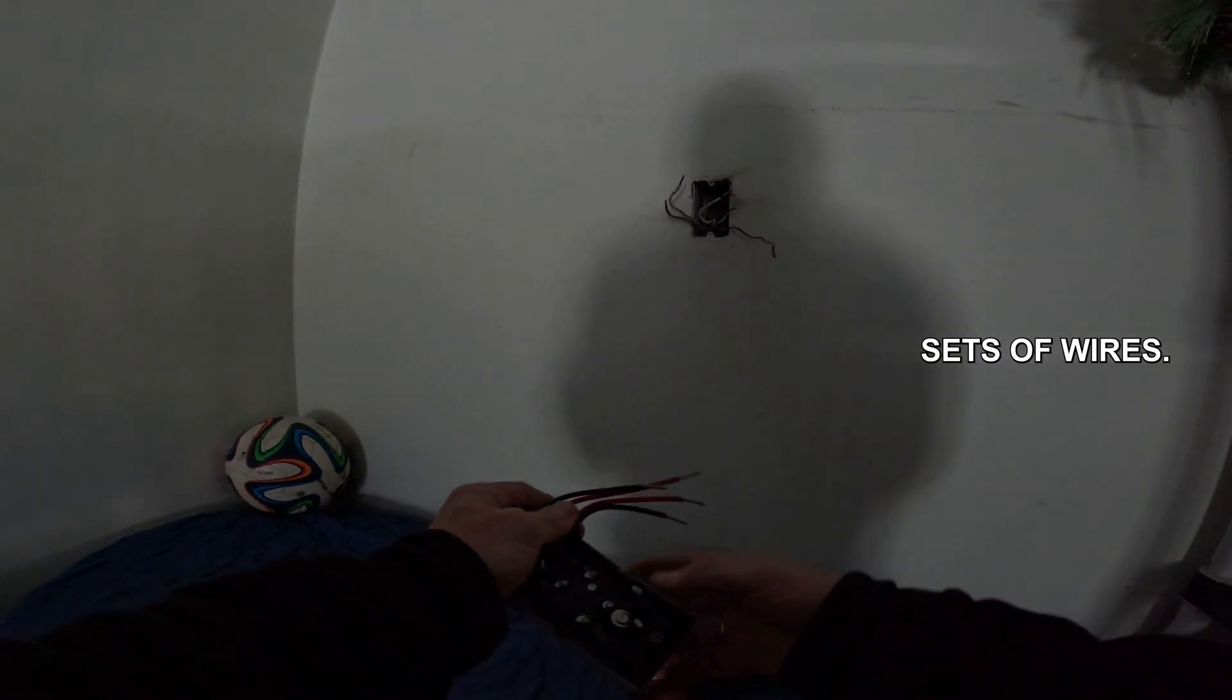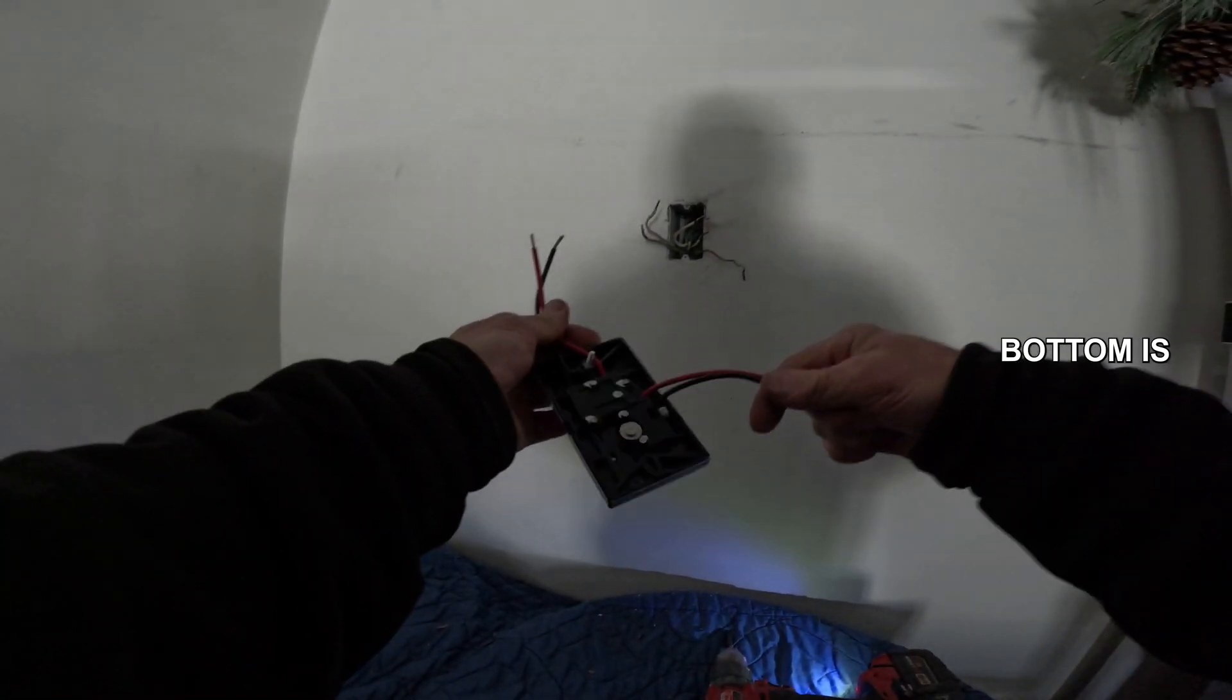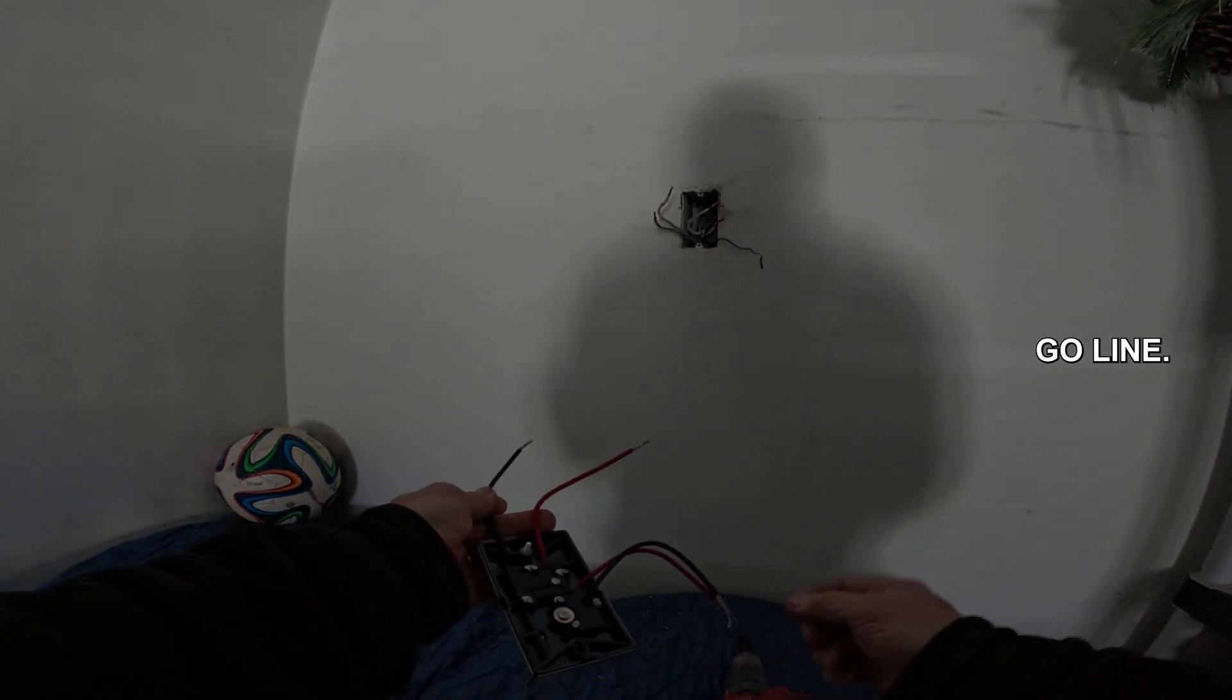You'll have two sets of wires. It'll also tell you on it if you look close, it'll say line is red, load is black. This top is a set and this bottom is a set. So you're going to go line. Remember line is red.